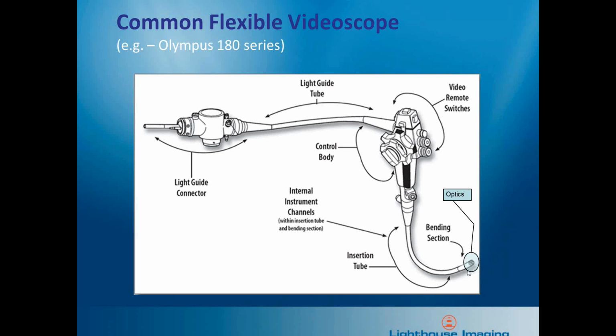Then when we get to the very tip of this scope, we get to the optics. So with these flexible scopes, they're very, very complex mechanical and electronic systems, but relatively simple optical systems. Out of this entire assembly, which may be 2 or 3 meters long, there's only maybe 15 millimeters at the tip of it that are optics. The rest of it is all mechanical and electrical, and some illumination fibers, but as far as imaging optics, there's very little.